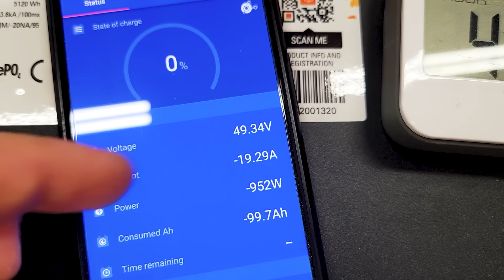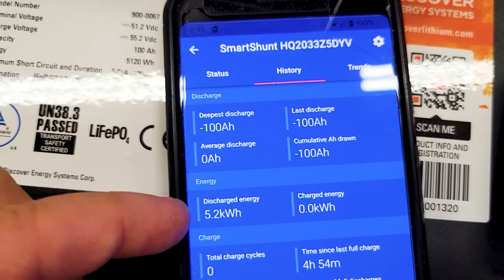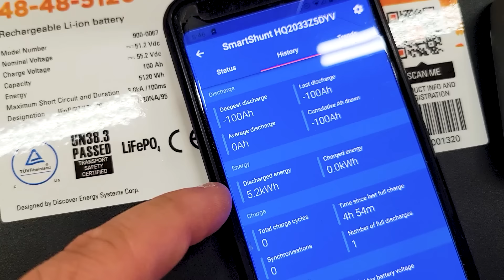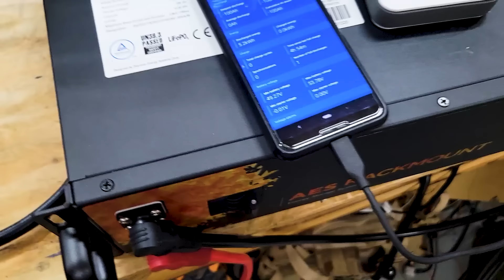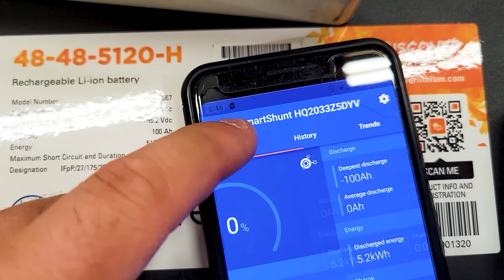We are almost done. 49.3 volts, still going a little under 20 amps at this point. And history, we've discharged 100 amp hours and 5.2 kilowatt hours. So we have passed the rating of 5.12 kilowatt hours, we've hit 5.2. So we've already hit our requirements, 100 amp hours, 5.2, excellent. So this battery has already met its specifications at just shy of 5 hours in this capacity test.